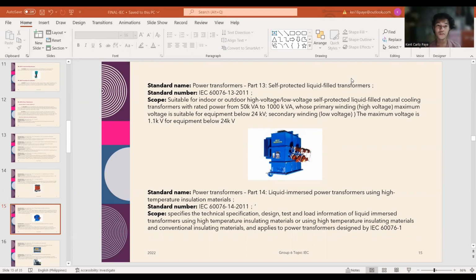So this standard is suitable for indoor or outdoor high voltage or low voltage self-protected liquid-filled natural cooling transformers with rated power from 50 kilovolt-amperes to 1000 kilovolt-amperes, whose primary winding, the high voltage, has a maximum voltage suitable for equipment below 24 kilovolts. And the secondary winding, which is the low voltage, has a maximum voltage of 1.1 kilovolts. Then the next parameter standard is the liquid immersed power transformer using high temperature insulation materials.